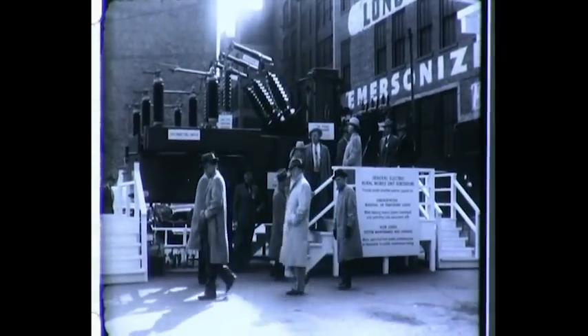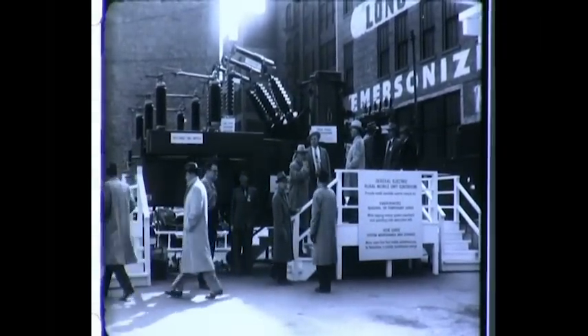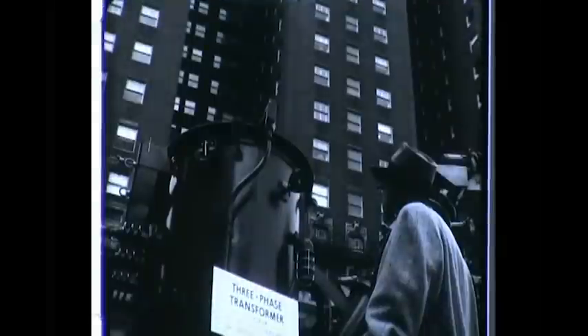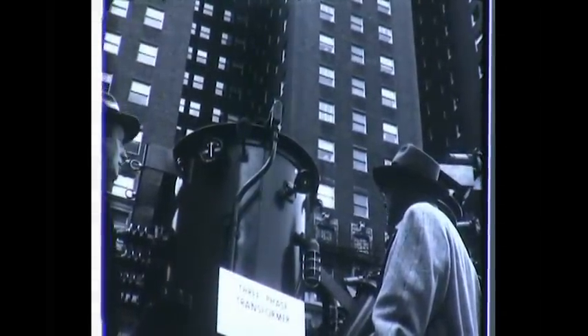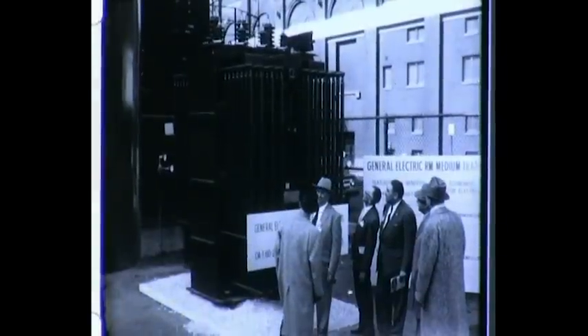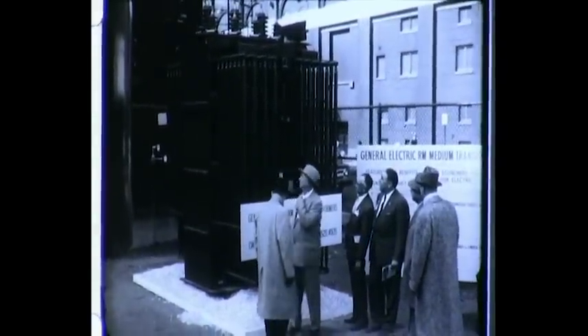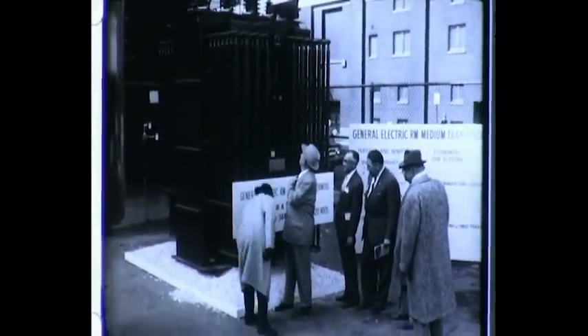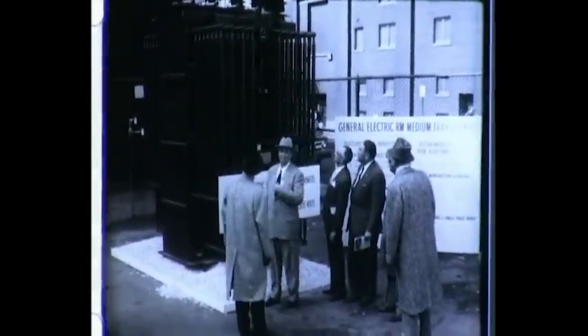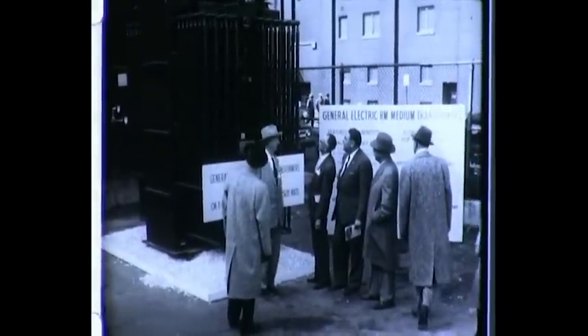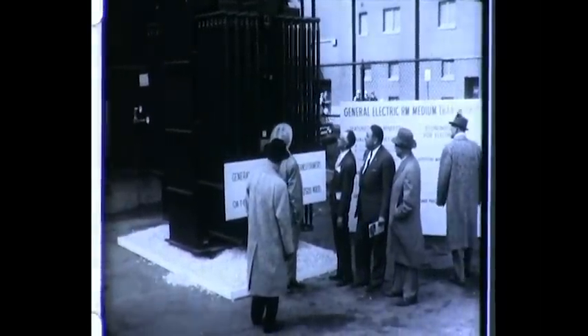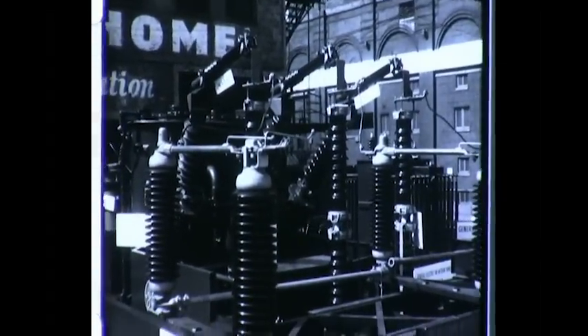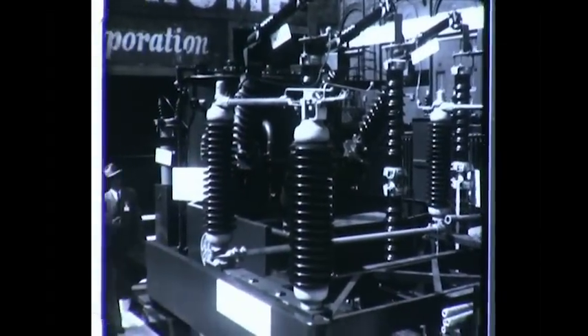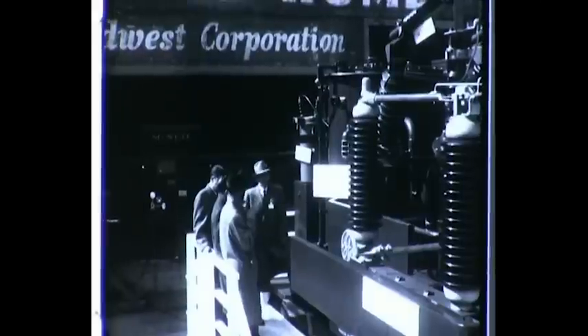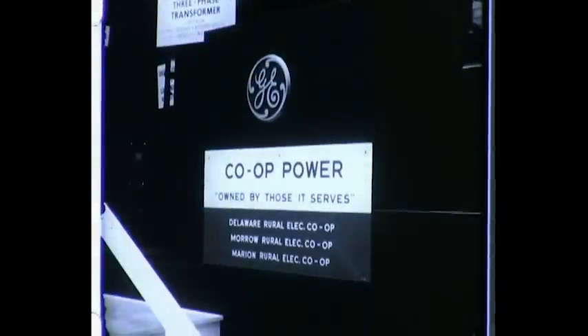Across the avenue from the main exhibit hall, General Electric set up its new rural mobile unit substation and three-phase RM transformer. When talking to your REA customers, remember that until recently, NRECA regulations required that REAs use 4 single-phase transformers in every substation. 3 of these were in actual use, and the 4th served as a standby or spare in case one of the others failed or was damaged.